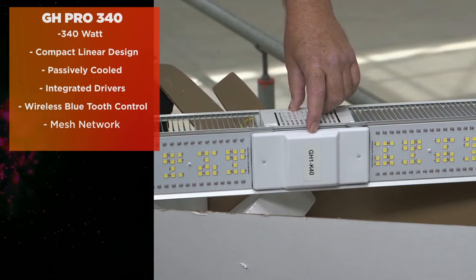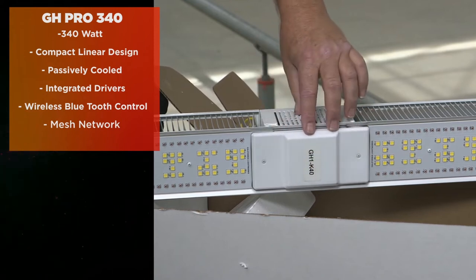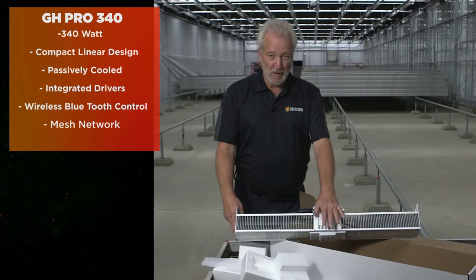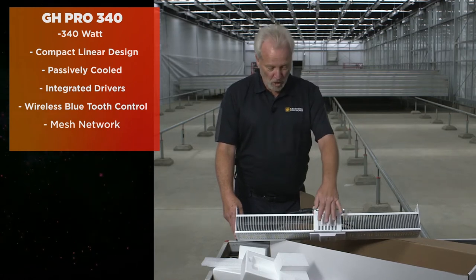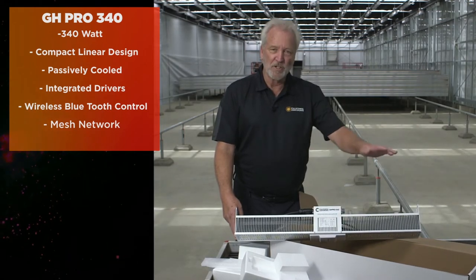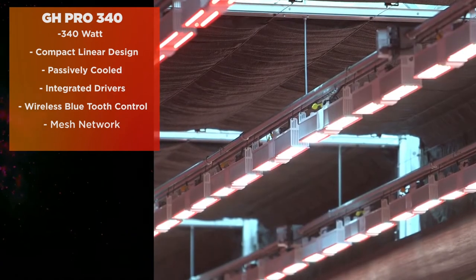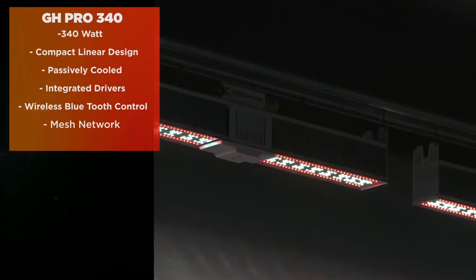This new Bluetooth mesh technology gives us the ability to link multiple sensors with multiple devices in a greenhouse, all communicating locally. Once programmed, the actual program stays in the local device so it doesn't depend on a controller sending commands. All of the routines are stored in the local device, and you can have intelligent communication between sensors and devices without going through a central controller. These can also run through a central program where intelligence could be in a cloud. We have a cloud service which will track data and allow commands of any zones automatically or manually.